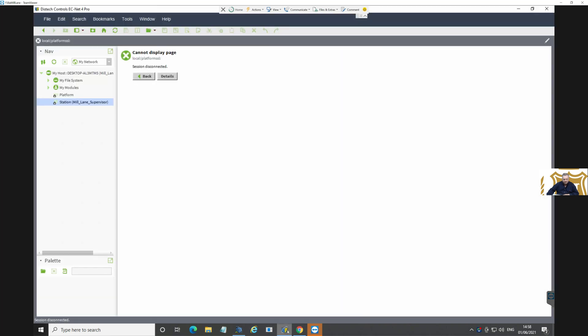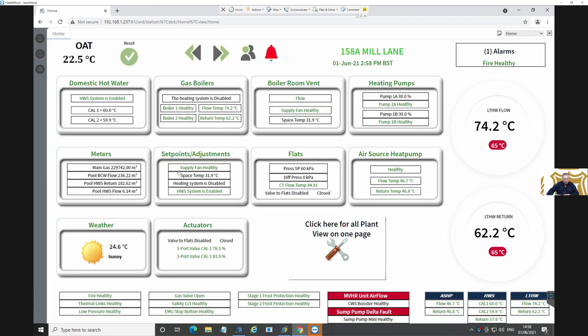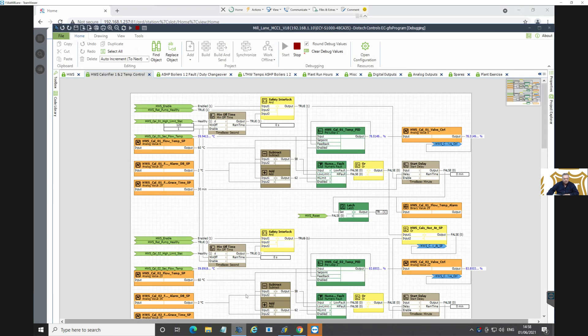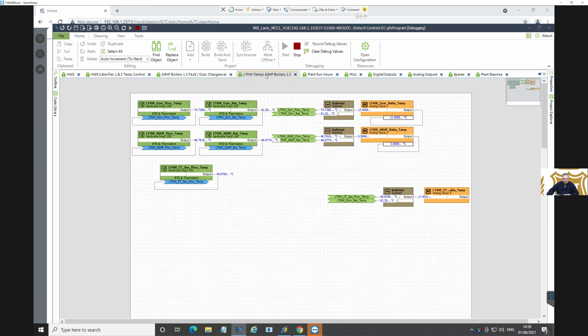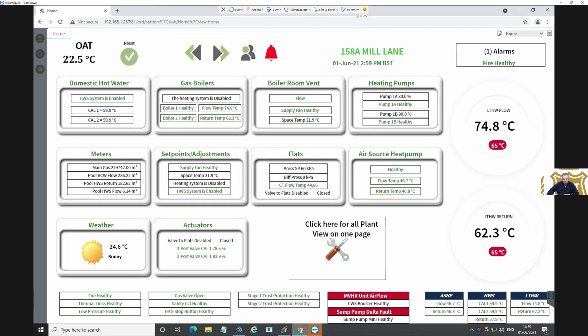Let's go back. That's their graphic - the controller. That looks about right to me. 74.2 flow, 62.2 return on the low temperature water side from the boilers. Common flow 74.2, return 62. There's nothing wrong there either.